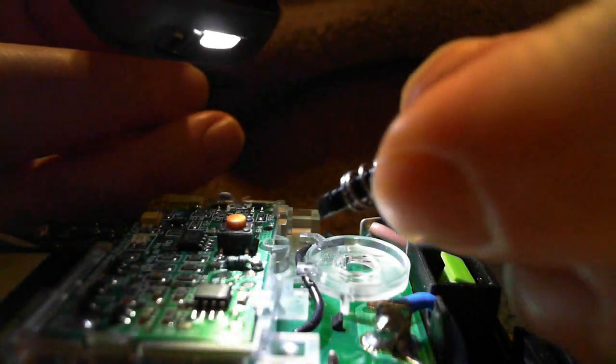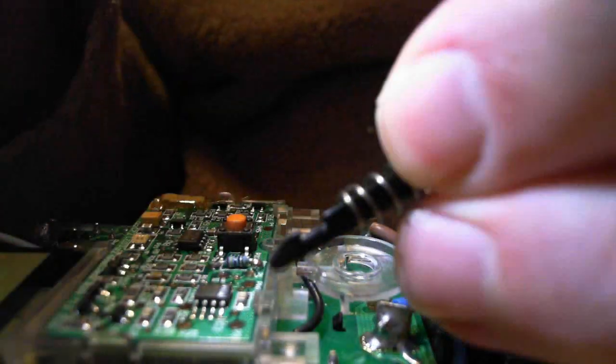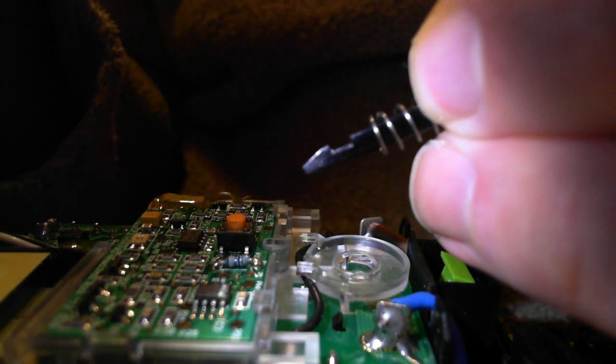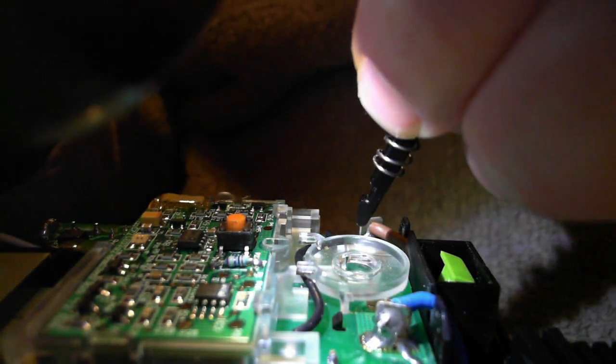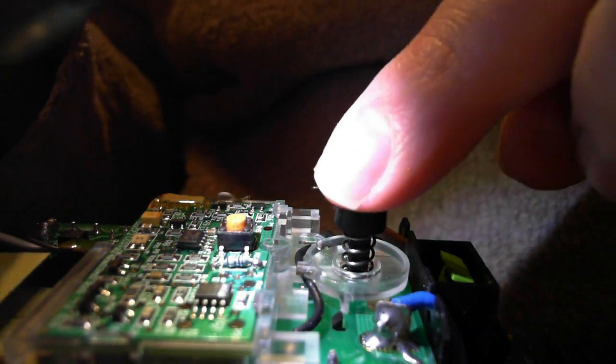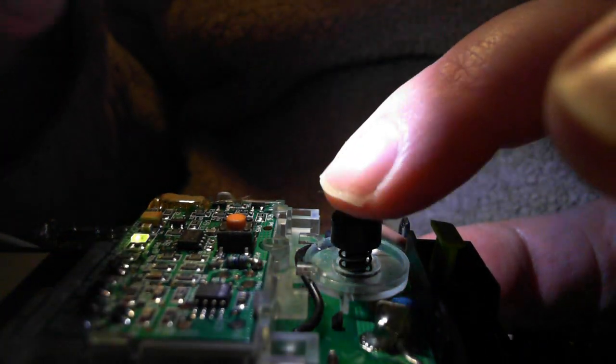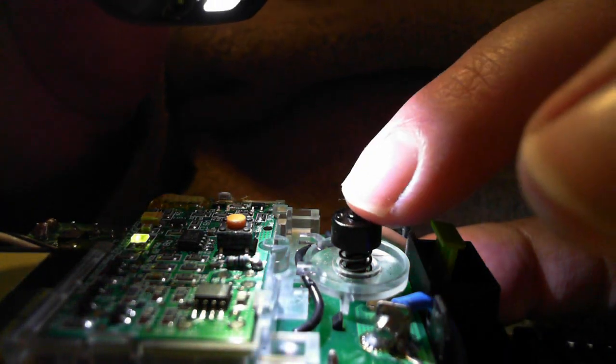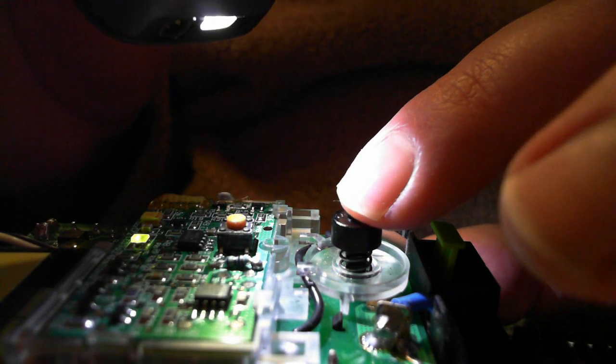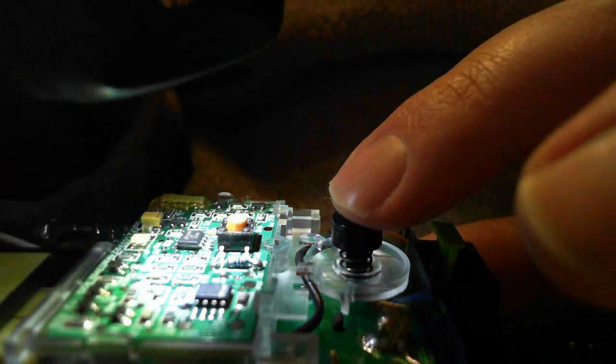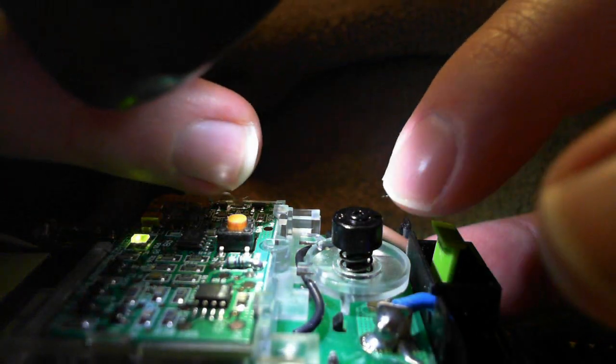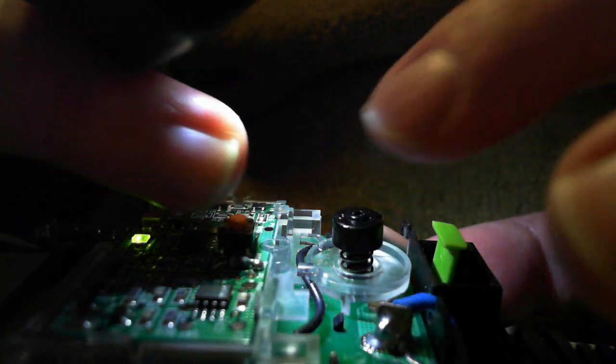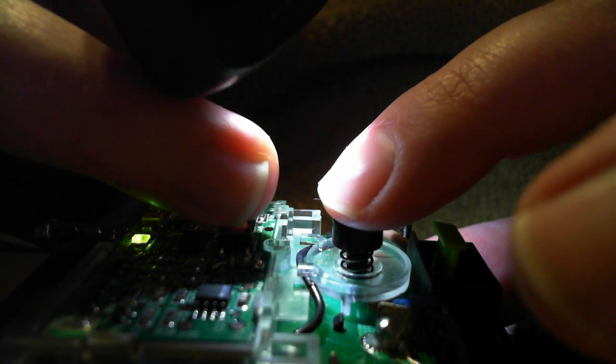Be careful of this piece here. This is a spring-loaded latch. This latch. If you press the test button while this pin is pushed in this way, without putting your finger over the top, this will catapult, be propelled at high speed up into the air. I lost my spring and had to scour the floor for the spring, so be careful if you're testing it with the cover off.